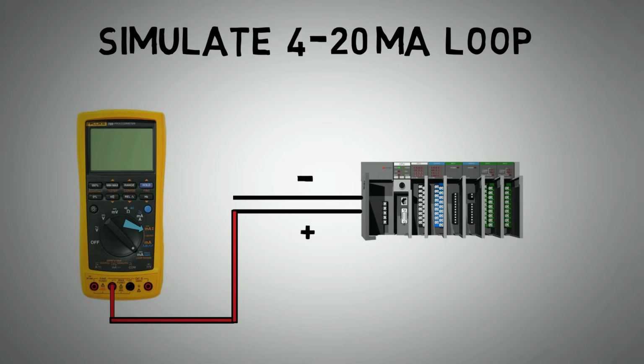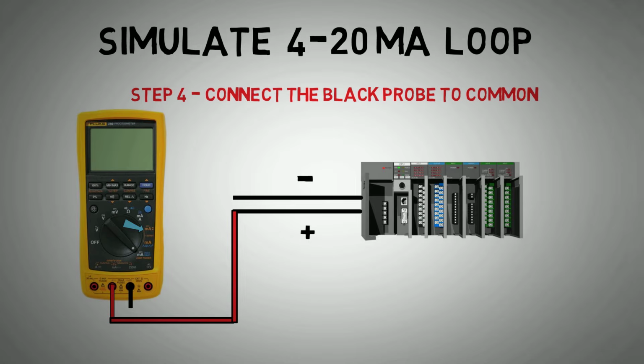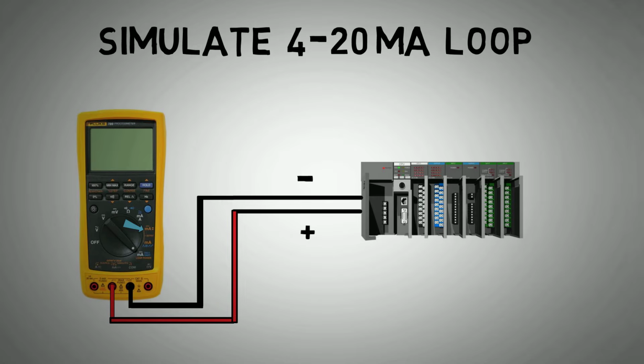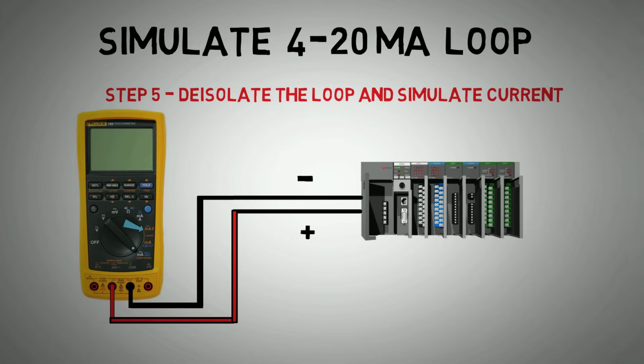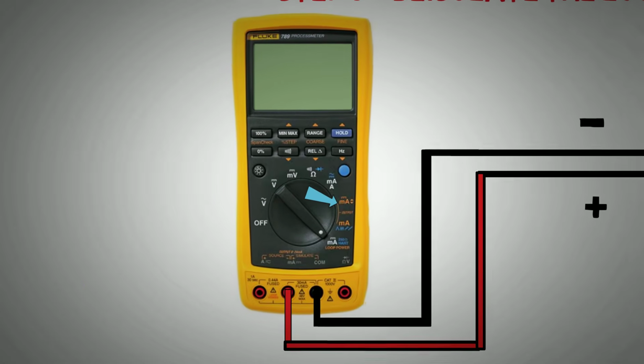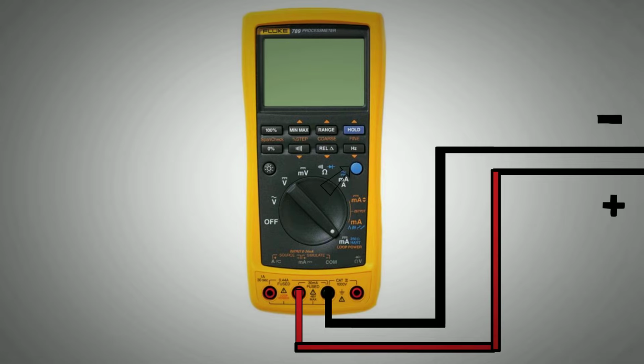Step 4. Connect the black probe to the common port on the meter and connect to the negative wire going back to your input card. Step 5. De-isolate the loop and you are now simulating current in the loop. Just like when sourcing, you can change the current setting with the coarse and fine buttons.